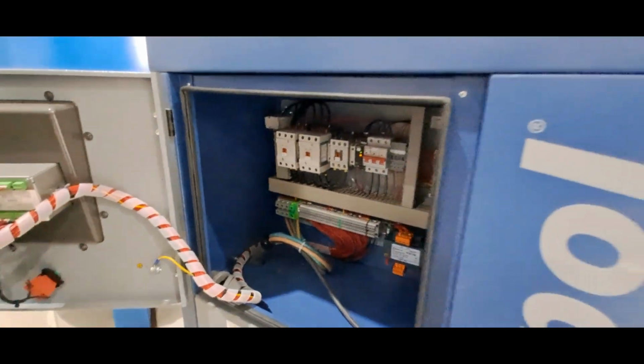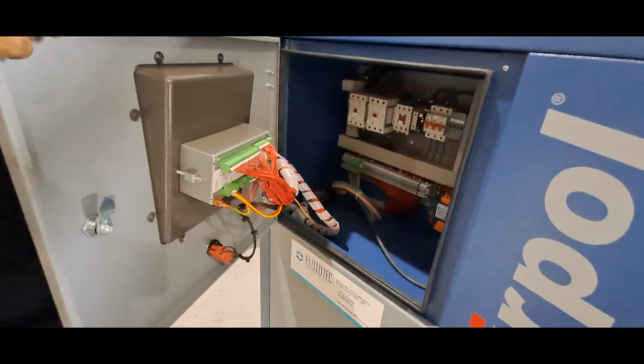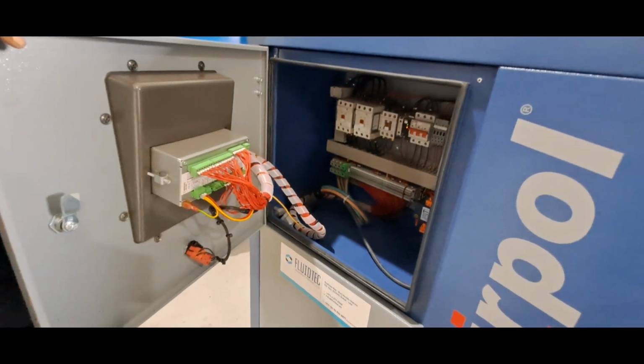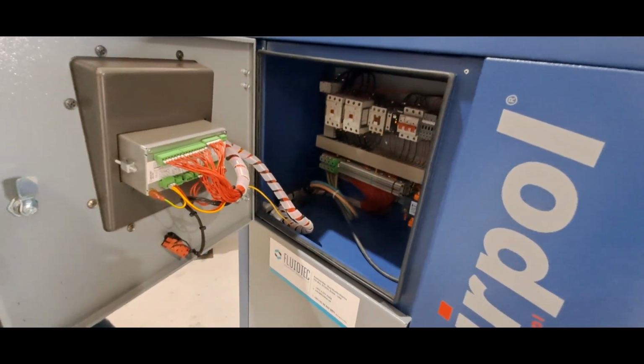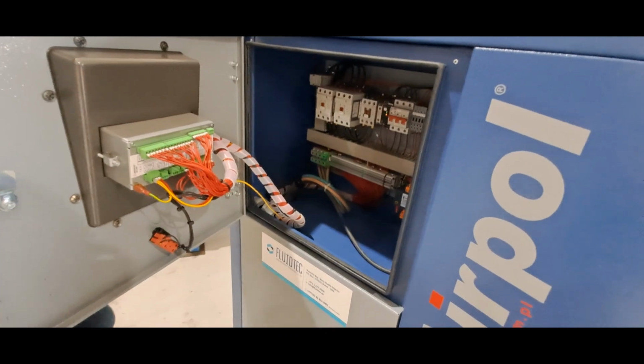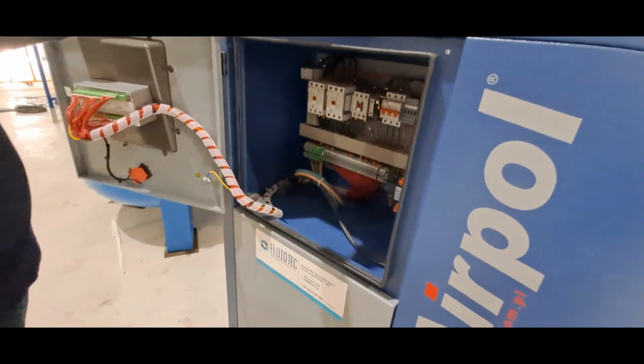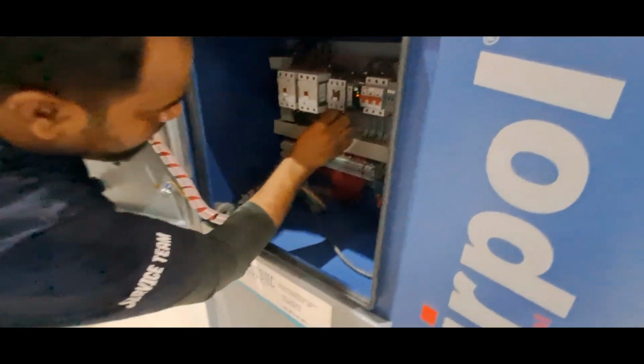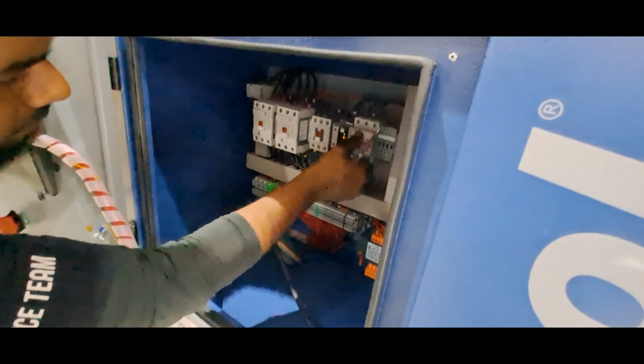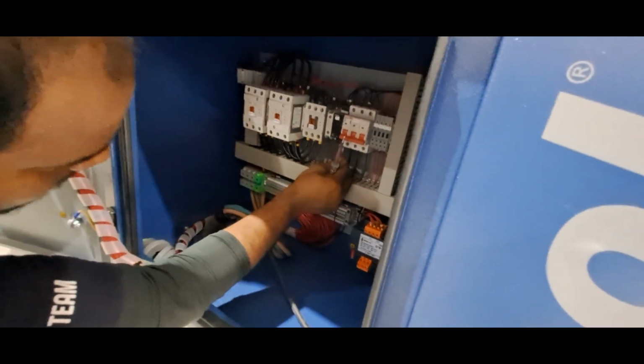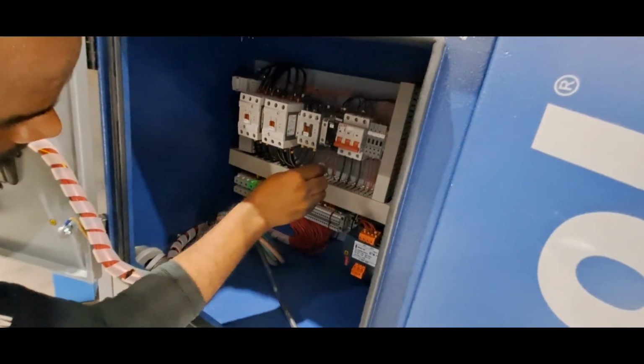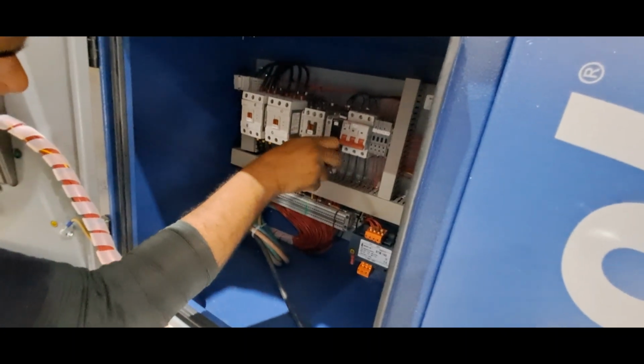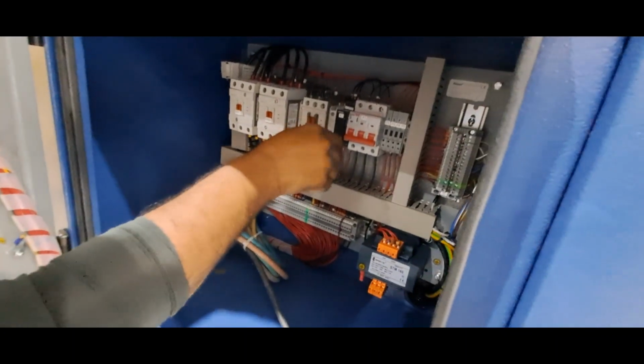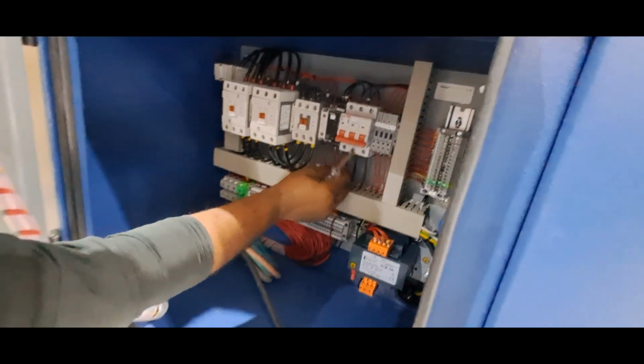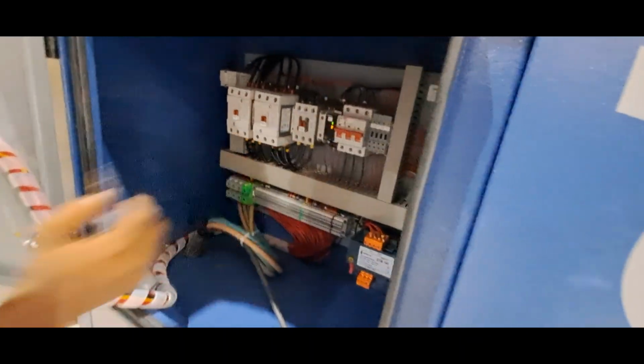Okay, so basically what he's saying is, if there is a wrong phasing, where you did not follow the right phase sequence R, Y, B, for example R goes to black or blue, the phase was changed. That will affect the rotation of the motor. If it is set to clockwise, the motor will run counterclockwise. So make sure the phase and the voltage are proper.